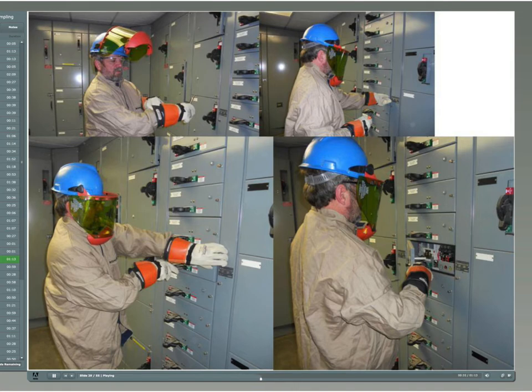Overprotection is better than underprotection. When in doubt, wear a 40-calorie suit even though an 8-calorie suit may be adequate. 40-calorie protection is better than 8-calorie protection. 8-calorie protection is better than just safety glasses and cotton clothes. Long-sleeve cotton clothes are better than synthetic. Never wear synthetic. The point being, breaking the law is discouraged. Reduce your risk. Minimal protection is better than none.